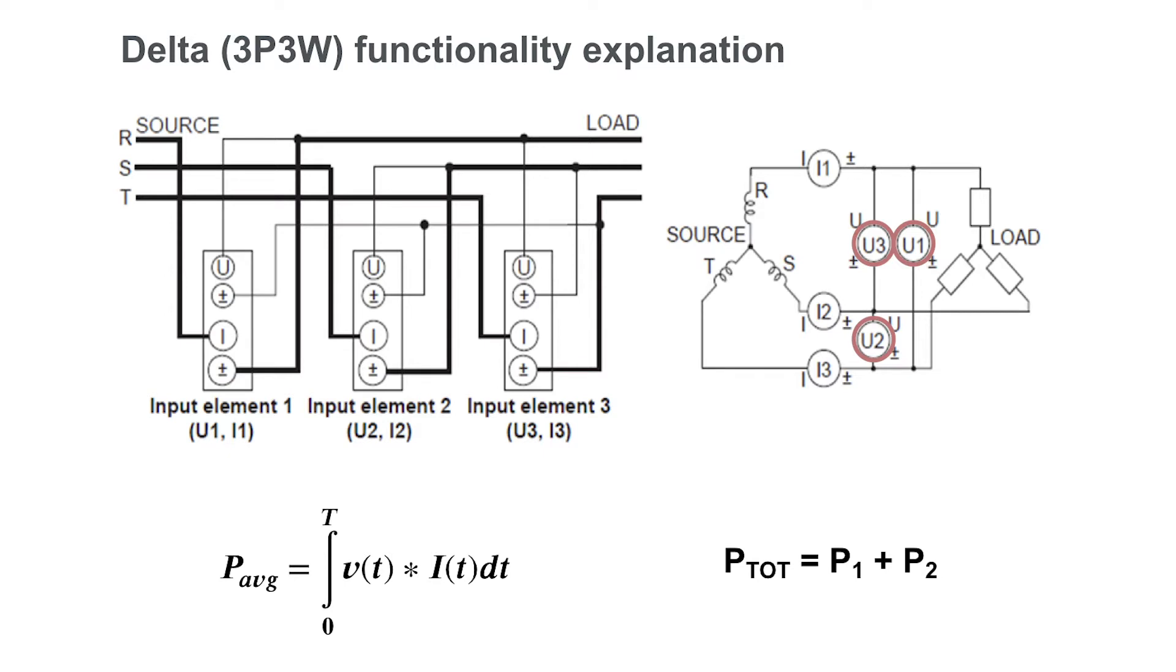In this wiring configuration, the measured voltage and current do not share the same phase relationship due to the lack of a common reference point, which is the neutral in the three-phase four-wire configuration. Because our voltages are no longer referenced to neutral, our individual power measurements are using those line voltages and will not be measuring the neutral-referenced individual phase powers.